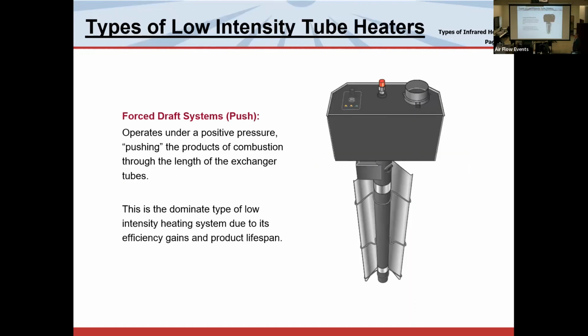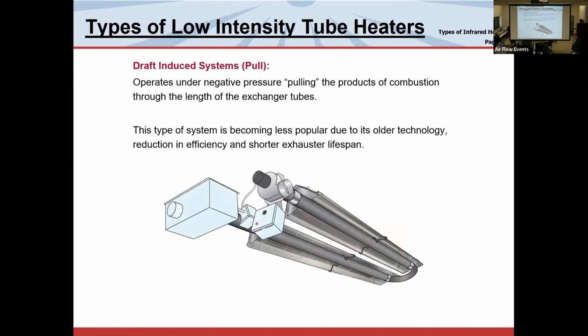Quickly, because this comes up in the market a lot, there are different ways to move the flame down a tube, right? The most popular and most economical way is we put a fan in that black box, the burner box, and it just pushes air down the tube that moves the flame. Next slide. Okay, the next slide shows an exhaustor motor at the end, okay? The exhaustor motor simply pulls it through the system. Now, our friends out of North Carolina, gas-fired products, they love to sell that this is a better way to move air, okay? But they can't explain why. The infrared output's relatively the same on either heater.